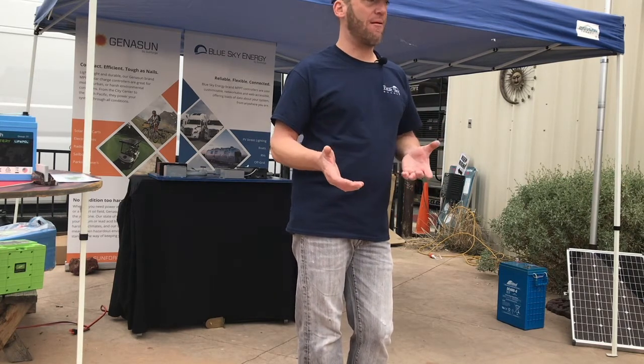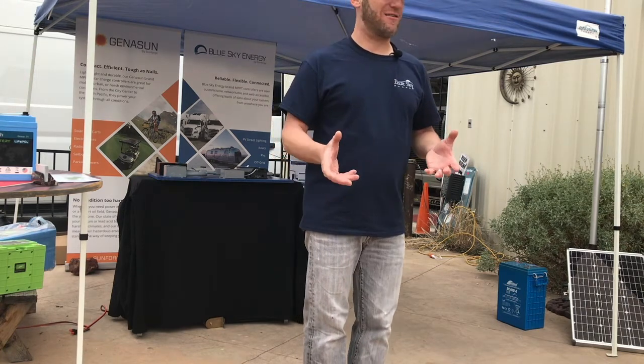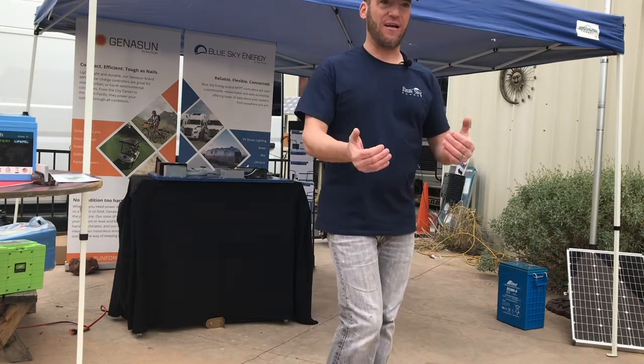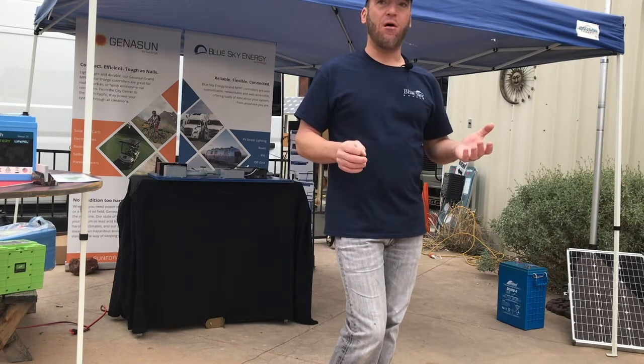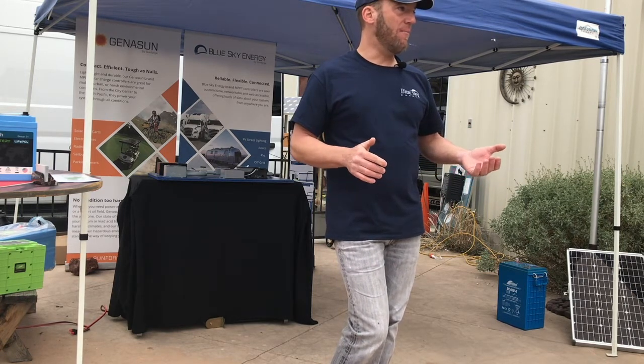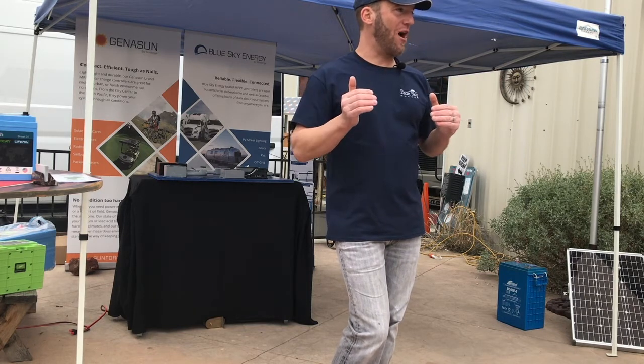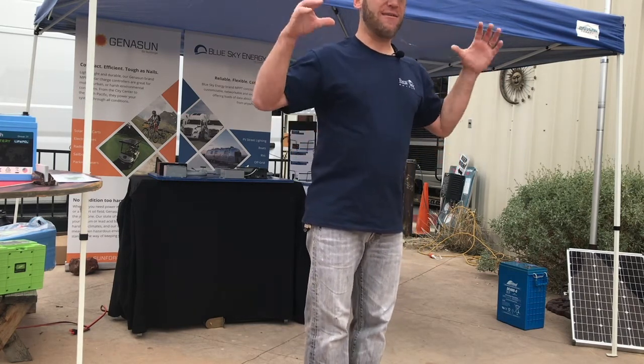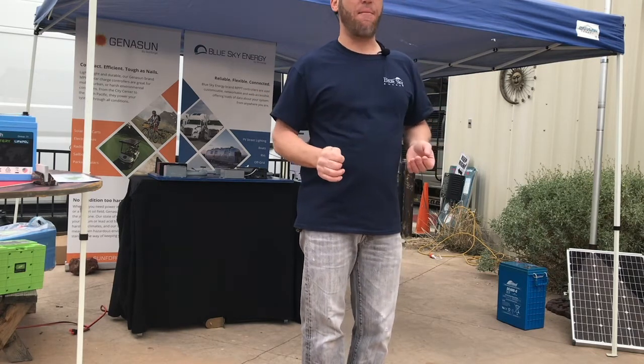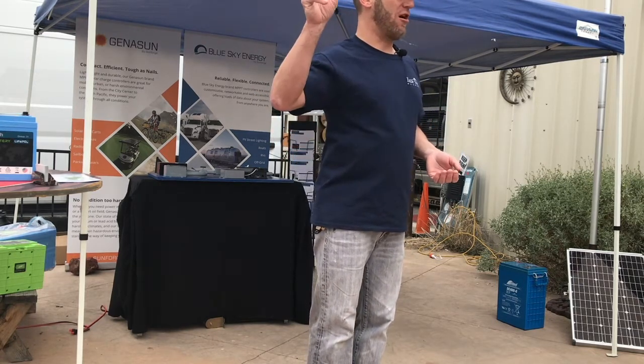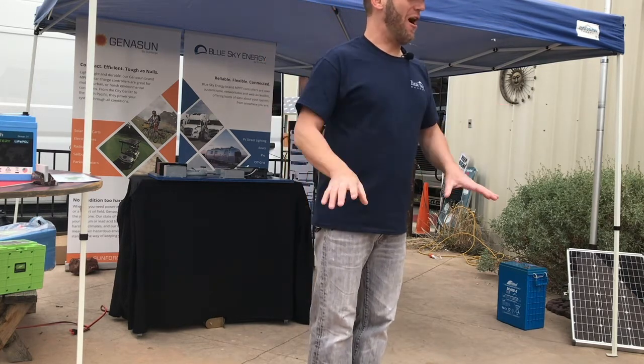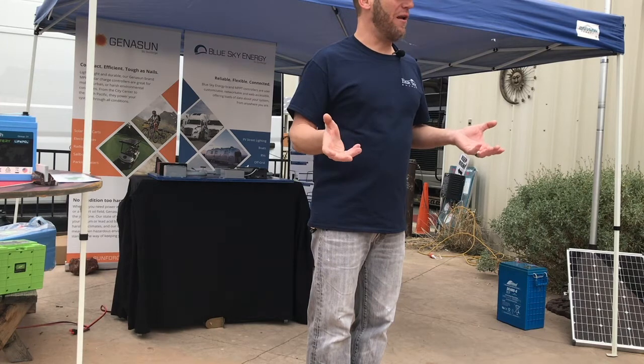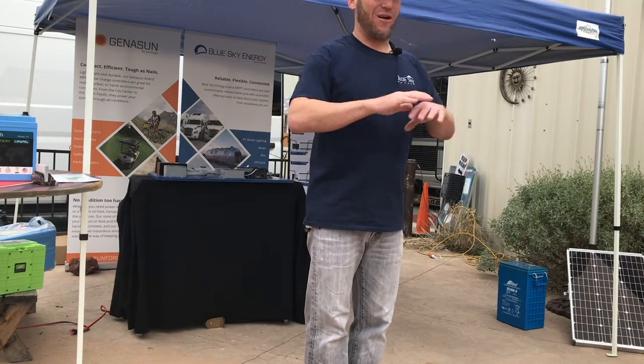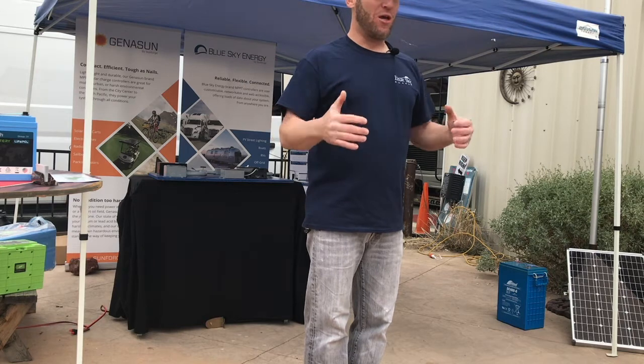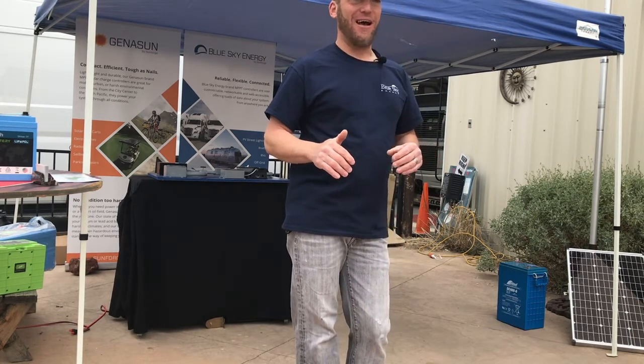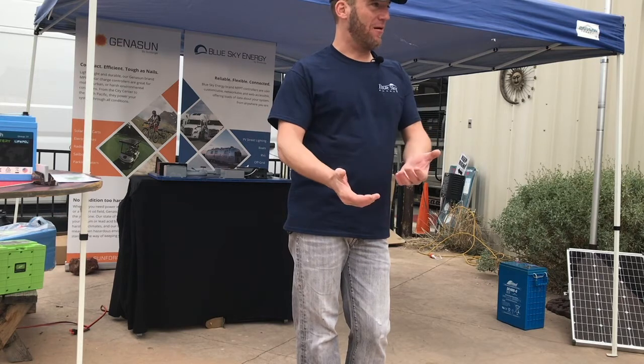We do sell our CBM, a current booster module, which basically acts like a solid state switch. It's a big relay. So we can increase that capability. I've had people, for example, run fans in their rig and set the voltages, because everything's programmable. A lot of times I'll have people with fans in their rig in storage mode, and they'll say, okay, when the battery is above 13 and a half, turn on the fans, and when it's below 13, turn off. What that means is those fans are only going to be on when your solar power is active and charging. And now if you covered the van or the panels got snowed over, your resting voltage is going to be below 13, and all of a sudden, your output's not available.